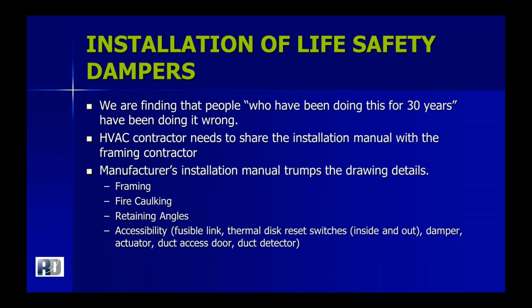So it's very important for an HVAC contractor to share the installation manual with the framing contractor. In the end, no matter what the design documents state, that installation manual is going to trump the design detail, as these are UL-listed devices, and they do have specific requirements in order to make them functional in the manner that they were tested. The manufacturer's installation manual discusses many details, such as the proper framing techniques, when fire caulking is required versus not required, retaining angles, including the screw depth, where they get screwed to, how often you need a screw through them, and accessibility. So we'll get into these a little bit more, but regarding the thermal links, the thermal disc reset switches or fusible links, access doors, your duct detectors, your sensing wands, and the damper itself, and the actuator.